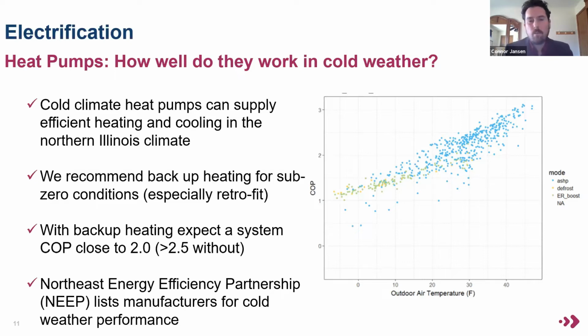Now, this doesn't really impact really well insulated and air-sealed buildings, but if you have a leaky envelope and your system doesn't have as much capacity when it's very, very cold out, that can start to become a problem. But even with including backup electric resistance heating, that annual system COP is close to about 2. So that means for every 1 unit of energy you put into that system, you get 2 units out in heating. So that's pretty good. So double the efficiency of electric resistance at the end of the day.